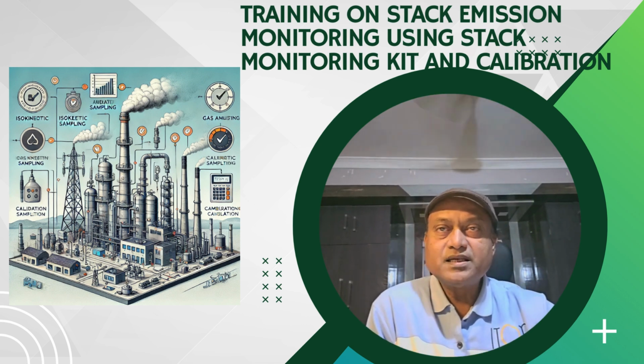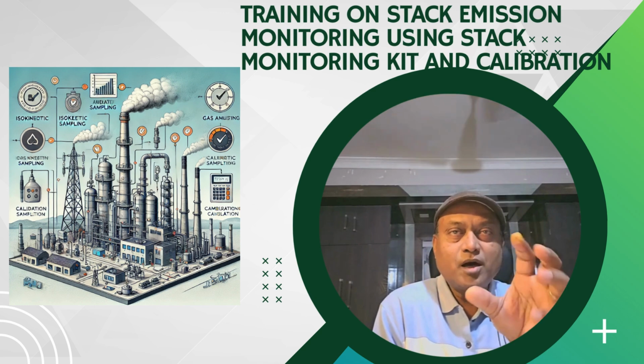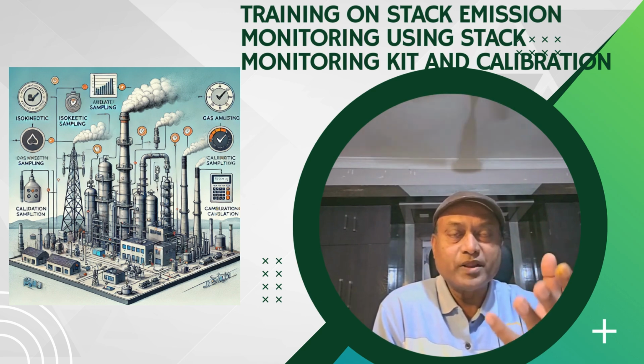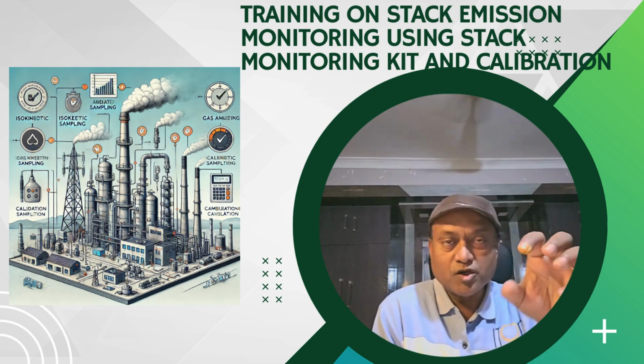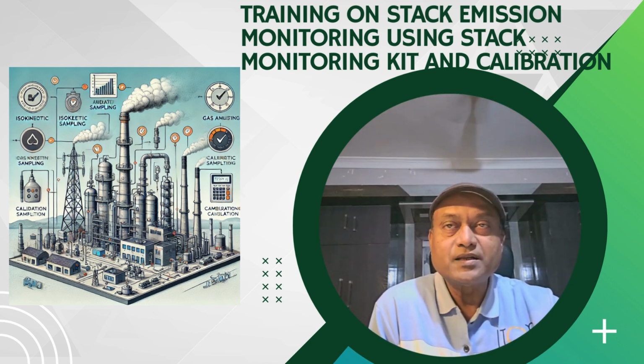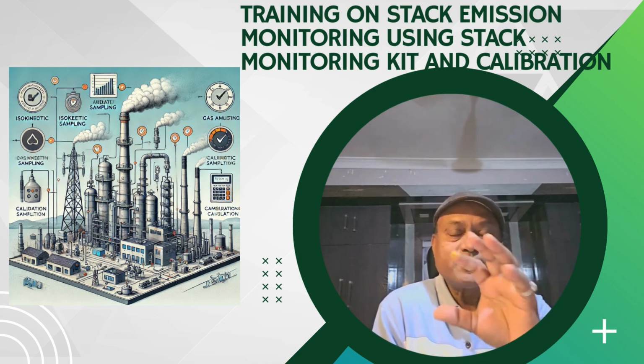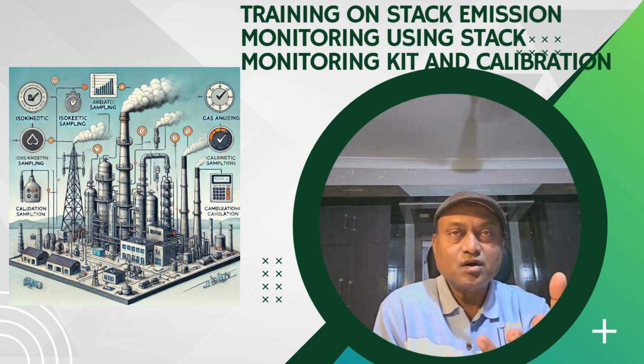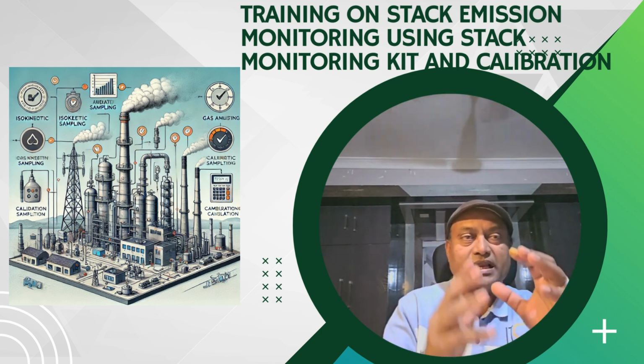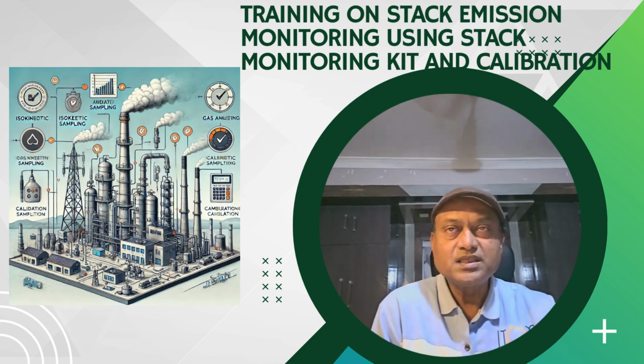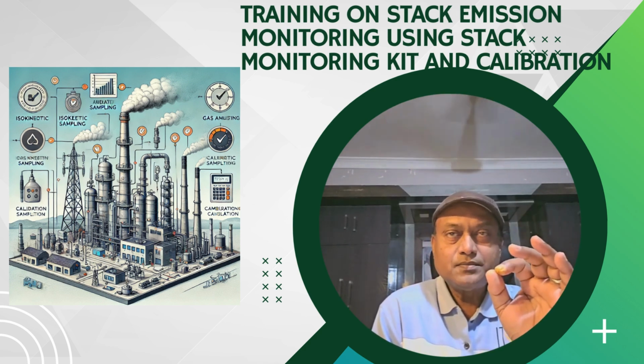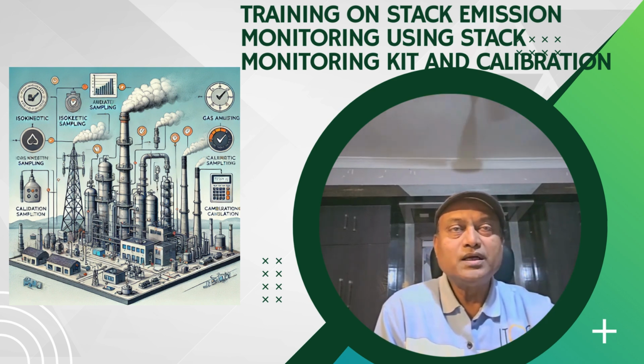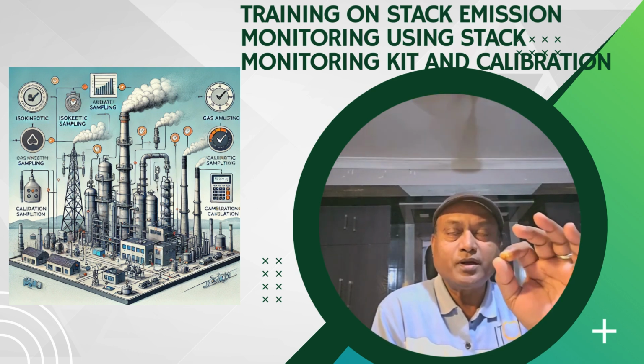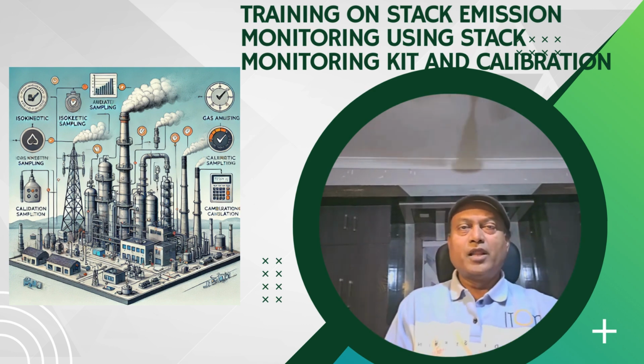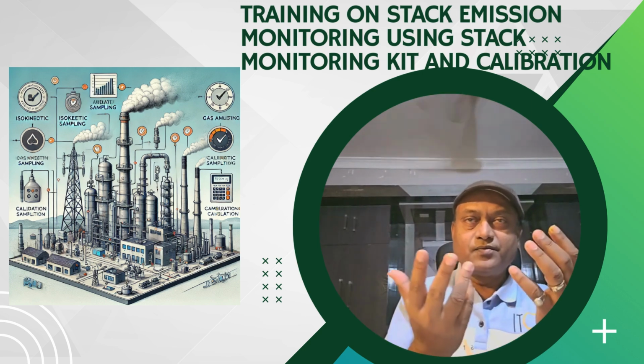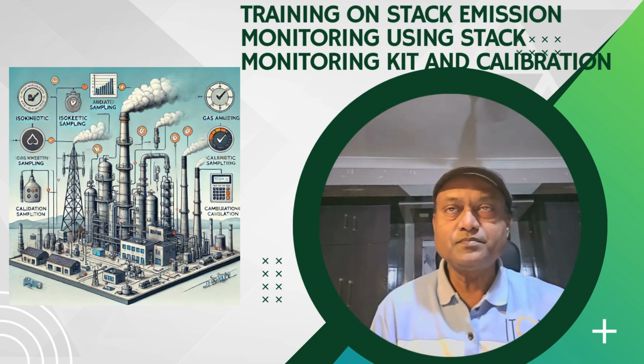Probe blockages: check for and clear any obstructions in the probe regularly during sampling. It may obstruct your sampling and withdrawing of the gases or particulate matter. Equipment failure: always have spare parts like filters and O-rings available, and check electrical connections every time. Calibration error: recheck the calibration gas and ensure that the correct concentration is being used for calibration. It is very important.